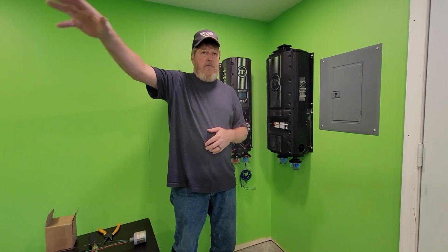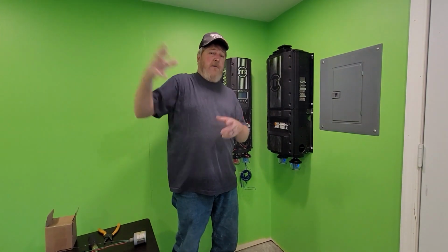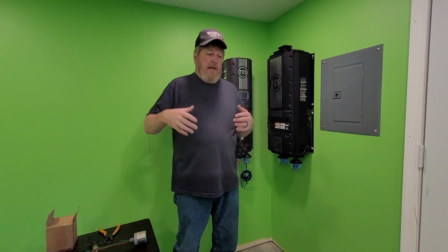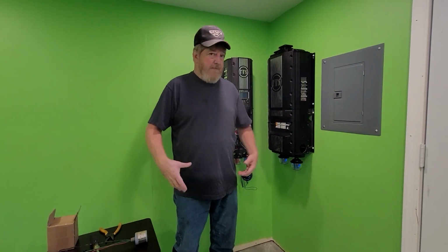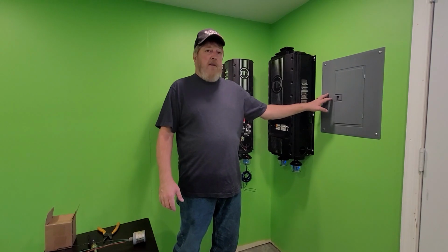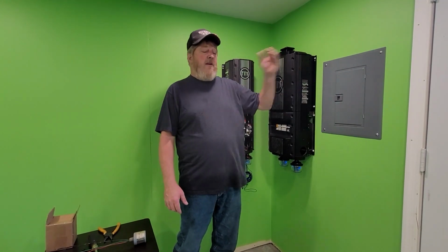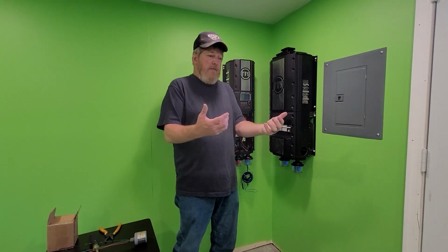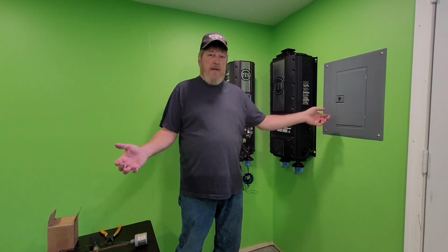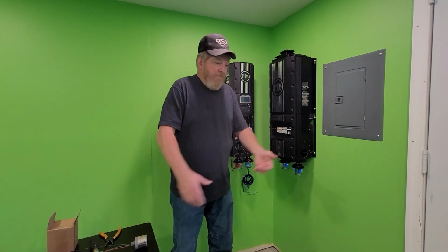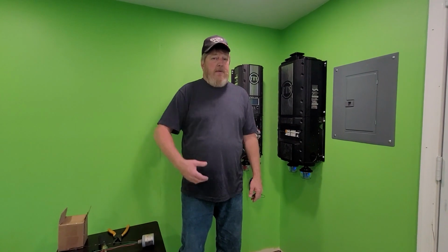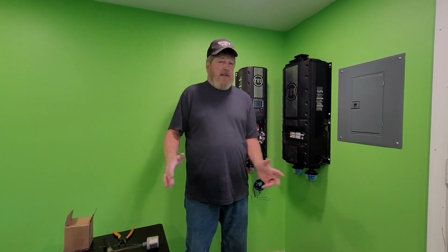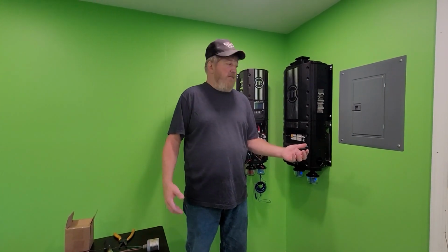So what I mean is, if you've got a building 100 feet away from your house and you feed a wire out there to a breaker panel, and you have something valuable in that building, you probably want a surge arrestor on that breaker panel, because that 100 feet of wire is an antenna and will pick up that voltage. If the only thing in that building is maybe a $20 fan or a $100 air conditioner and nothing else, then you may decide it's not worth the extra cost.